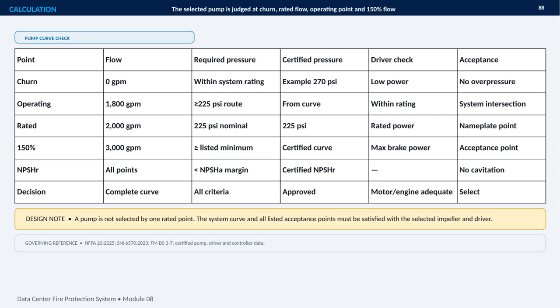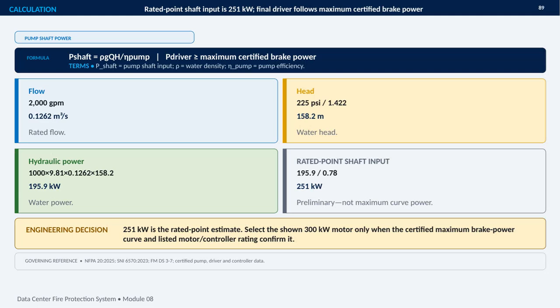The review also includes NPSH at all points, ensuring adequate margin to prevent cavitation, along with confirmation that the motor or engine can provide the required power. The final decision is based on the complete certified curve, the selected impeller, the driver, and the controller, not one isolated number. This evaluation follows the governing references listed here, including NFPA 20, SNI 6570, and FMDS 3-7. This slide calculates the pump shaft input at the rated operating point, then explains why that number alone does not determine the final driver selection.